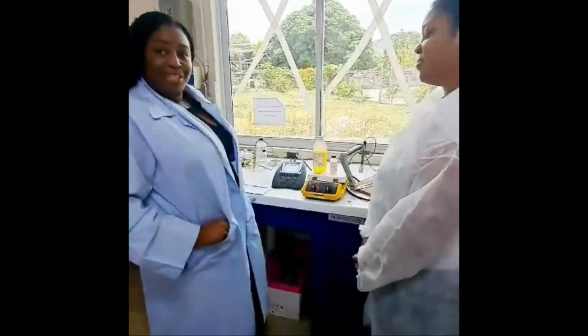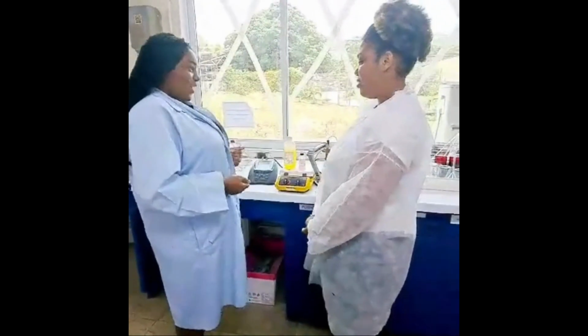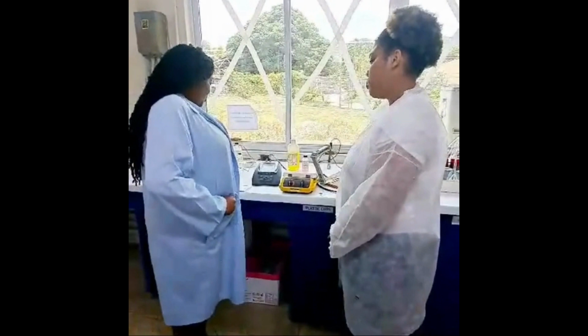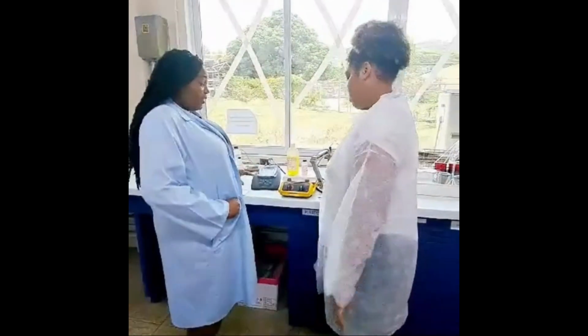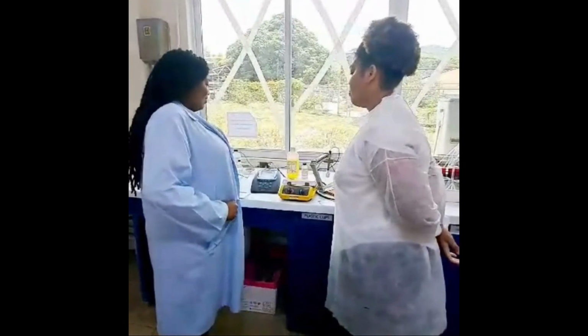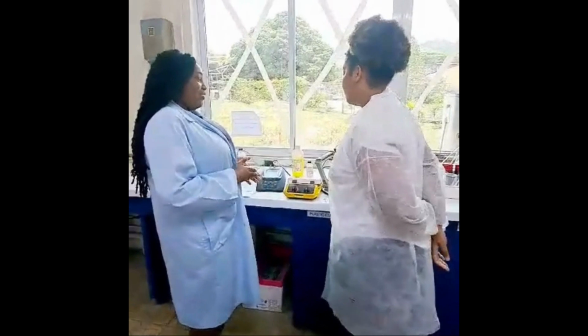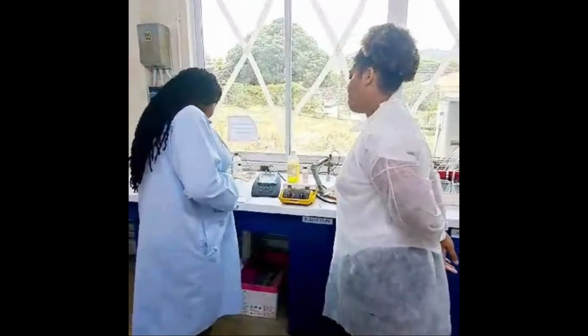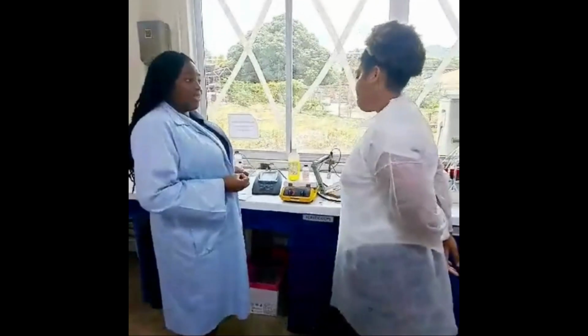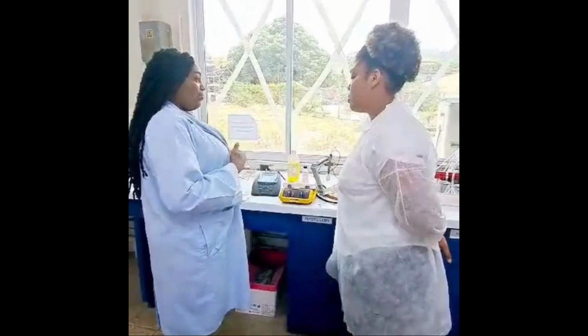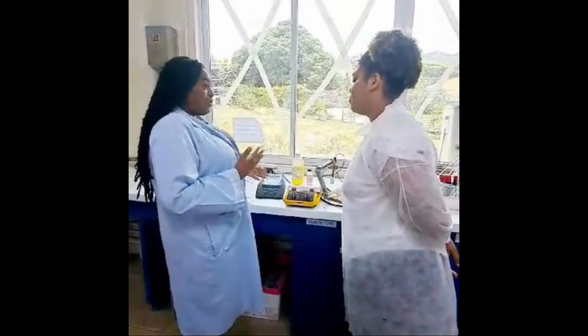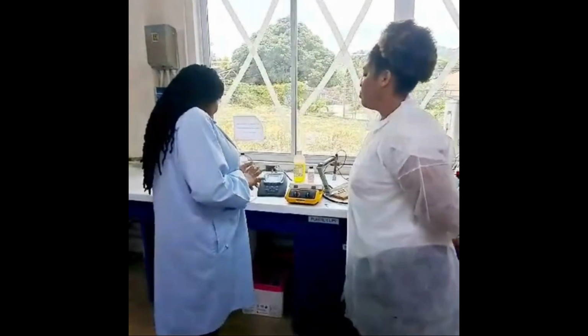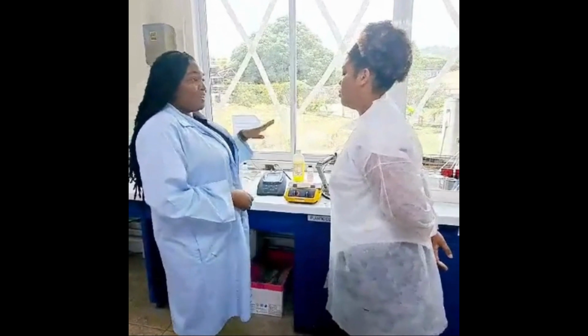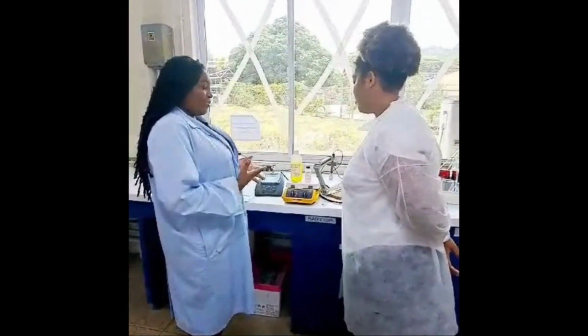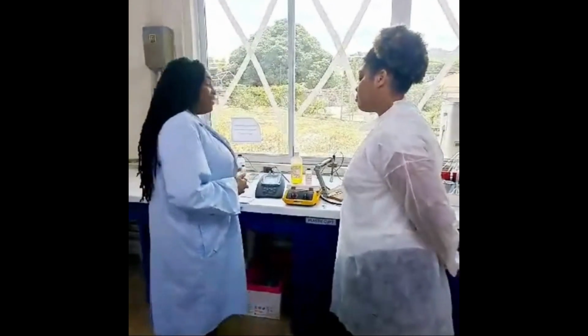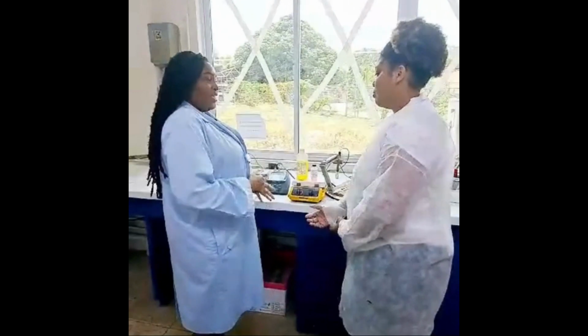So for this training session, we have a few objectives that we hope you will achieve. The first one, we want you to calibrate this pH meter using the buffers that we are using today. You should be able to do it with about 90% accuracy. If you fall short, then I will assist you. You would also need to say whether or not it is a good calibration based on the slope that you get and the limits provided for the slope. Also, I would want you to appreciate the importance of cleaning the probe before transferring it to the different solutions. And finally, I would want you to be able to measure the pH of a paracetamol solution with 100% accuracy.